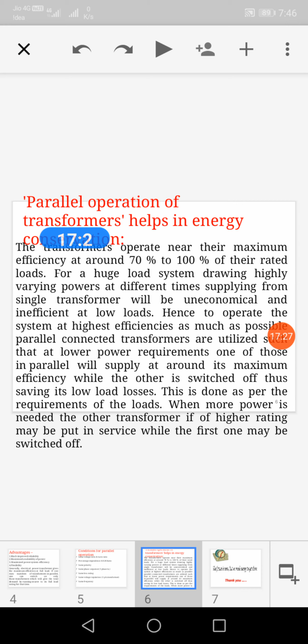And then I explained flexibility. The possibility of increase or decrease of demand in future can never be ignored in a power system. The provision of connecting a parallel transformer to meet increased demand keeps the system flexible. Installing a single transformer of greater capacity by forecasting future demand may prove an unnecessary investment, which may or may not be worthwhile. Also, in case of decrease in demand, the capital investment and its return can be balanced by simply removing a transformer, and that is the added flexibility of the parallel option.